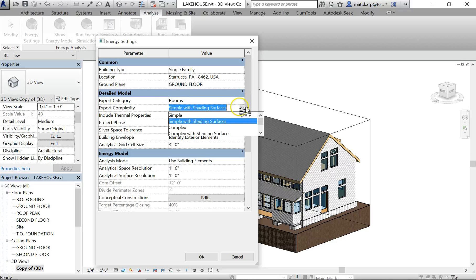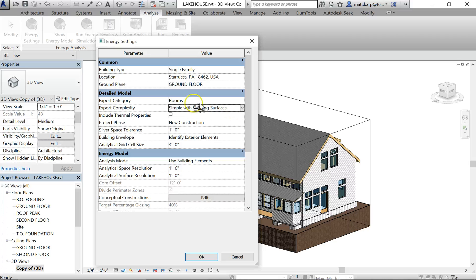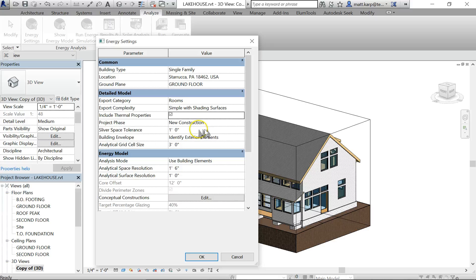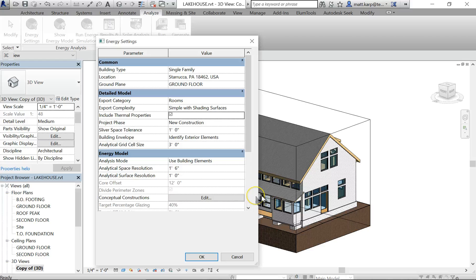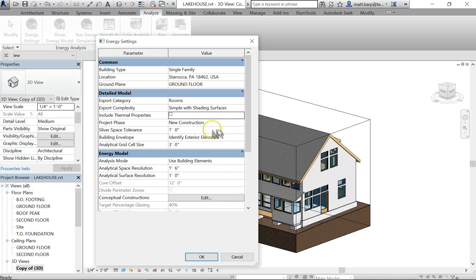You can pick the complexity. I'm going to do simple with shading surfaces, but you can do more complex and that would bring out the mullions and everything. But for now, simple with shading surfaces. Thermal properties - if you have set all of your pieces, click that. If you have set all of your materials that have thermal properties so you have R-values for your walls and roofs, you can set that. If not, it's going to guess at what the average pieces are. So if you didn't set up all that, just don't click this. We can always override it in Green Building Studio separately from this.